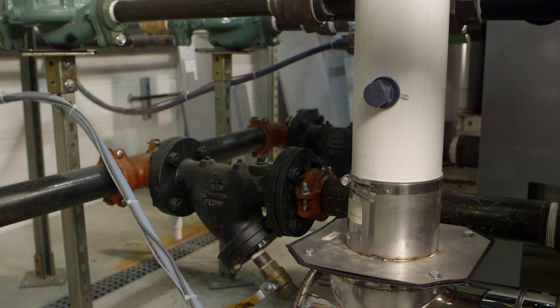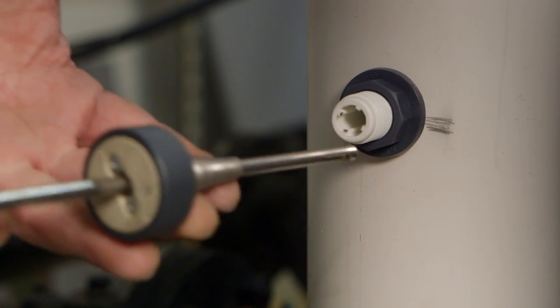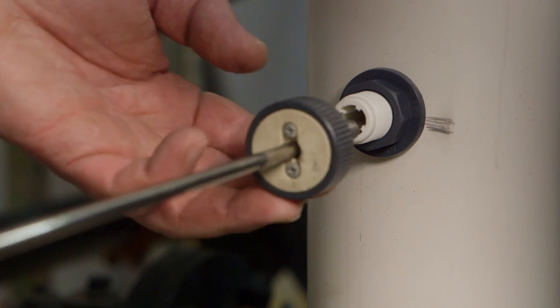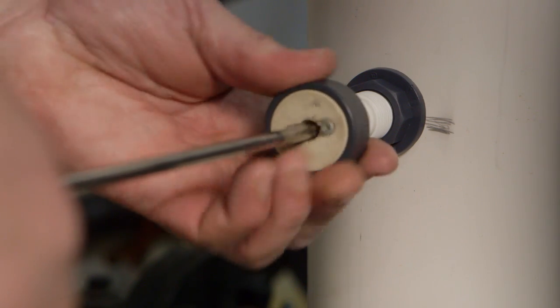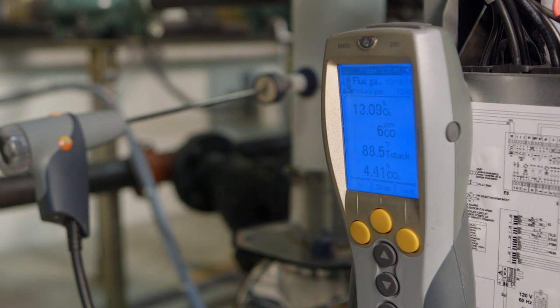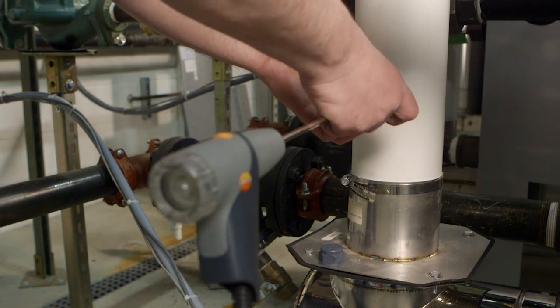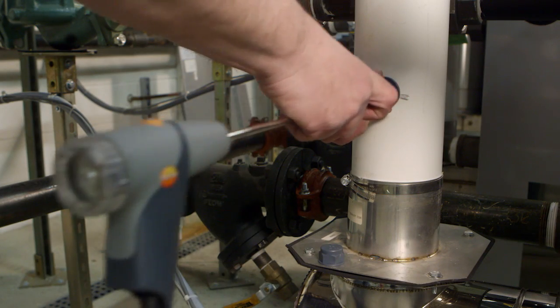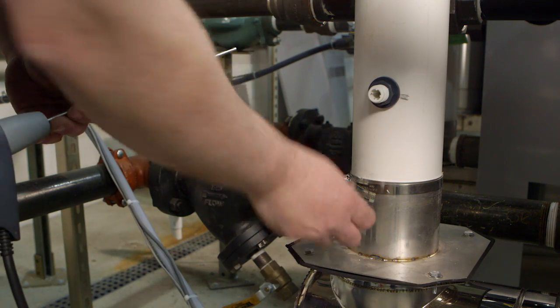Before you make adjustments to the boiler, a gas analyzer sensor probe must be installed into the flue exhaust outlet. First, remove the cap from the gas outlet. Next, install the probe adapter into the gas outlet as shown. After you've taken measurements and made your adjustments, remove the probe adapter, and reinstall the cap onto the gas outlet as shown here.